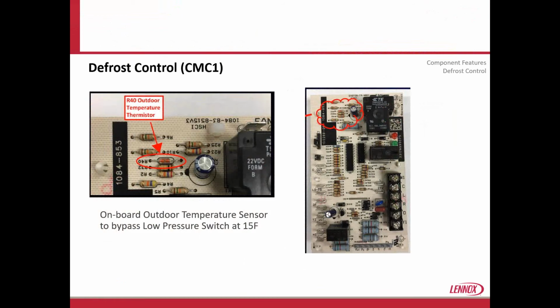We also have upgraded the board on the Dash 4 models and up. So everything that you're going to see out there has a built-in temperature sensor on the board. We did this basically for the package unit. When the package unit first came out, the Dash 1, several years ago, when we converted to the new model we're talking about, we had some issues when it was really cold out: it went into defrost and would actually kick the low pressure switch. So anything below 15 degrees outdoor ambient temperature, we automatically no longer look at the low pressure switch.